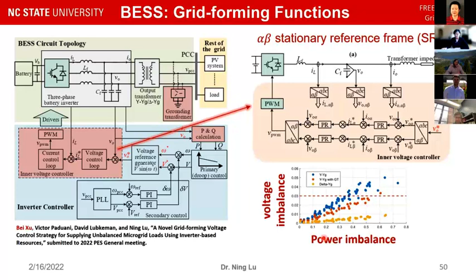If we add a grounding transformer to the system, we can effectively shift the power imbalance threshold from about 0.3 to 0.5. This is why we suggest that if we have a three-phase inverter, we put a grounding transformer here, which allows us to supply loads with more imbalance.